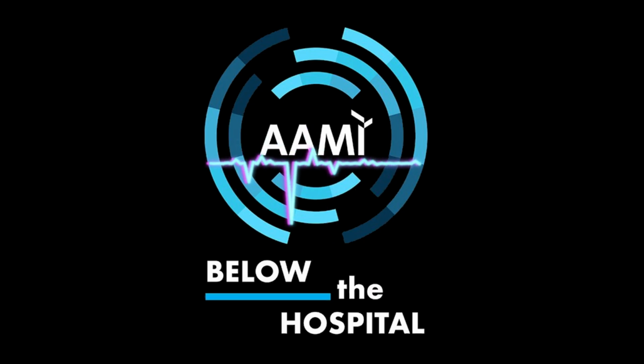So the main difference is that gamma uses radioactive substances. It uses cobalt-60 to provide the radiation for sterilizing products. So the cobalt started off as cobalt-59. It's placed in a nuclear reactor for a year and a half to 2 years, and it absorbs a neutron and becomes cobalt-60, which is a gamma emitter. So it uses photons to sterilize. Both X-ray and electron beam are machine-generated sources. So plug it in, it works. You unplug it, it doesn't work.